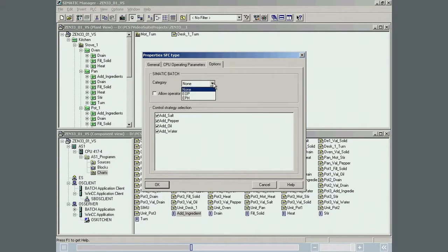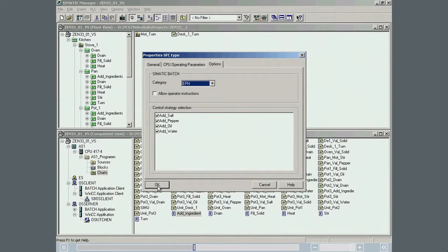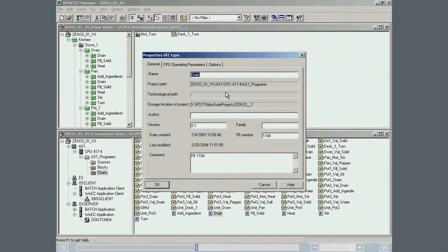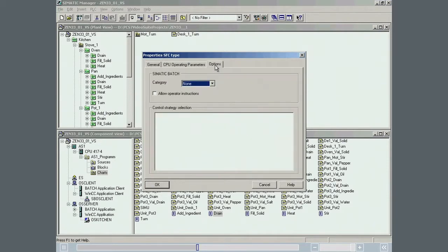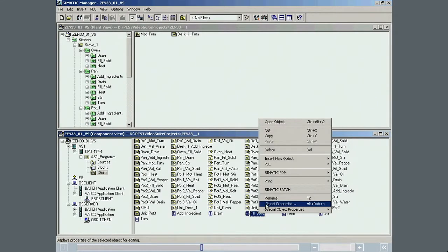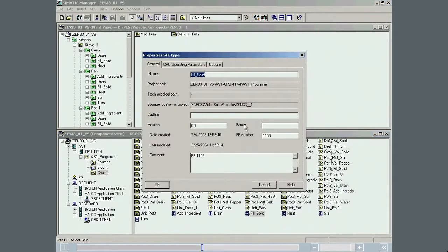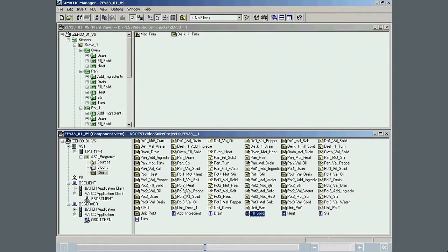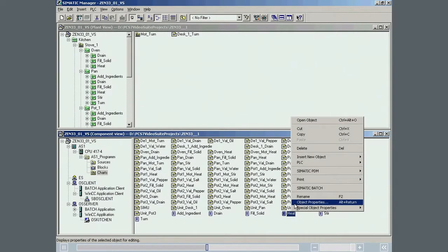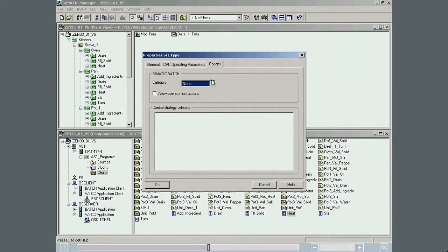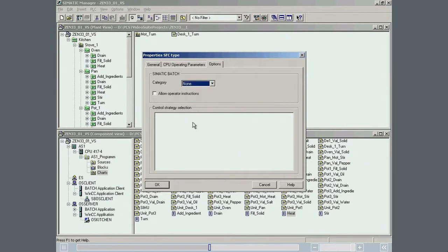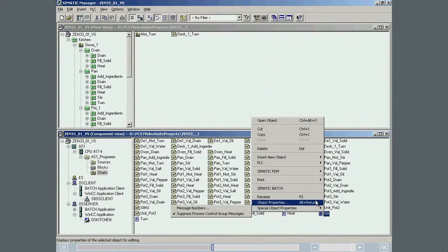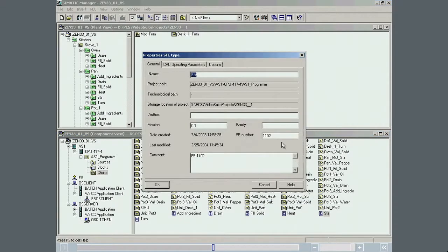A further SFC type category that is available for selection is the Equipment Operation, or EOP. This ensures conformity with ISA-S88. The difference between the two is that an EOP is linked to a recipe operation in hierarchical recipes, and an EPH is linked to a recipe phase. In general, the scope of an EOP is more extensive and more complex than an EPH. Creating recipes using EPH allows greater flexibility. EOPs are useful when the equipment functionality is fixed.